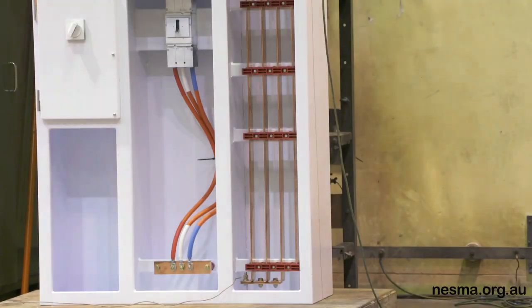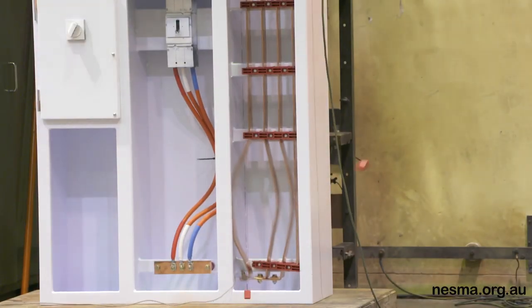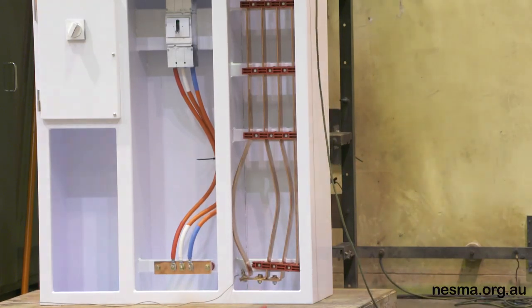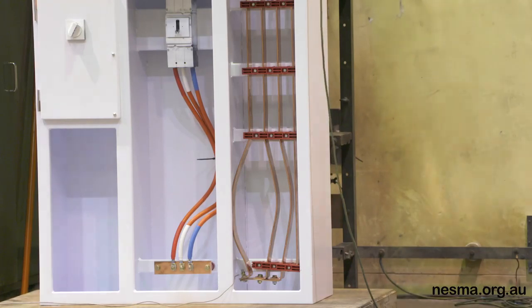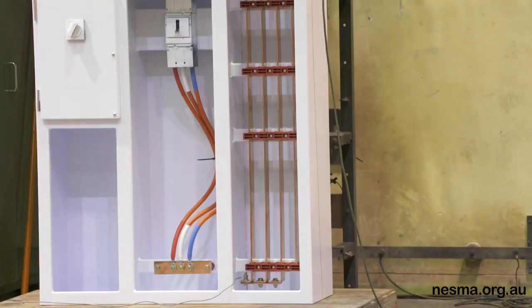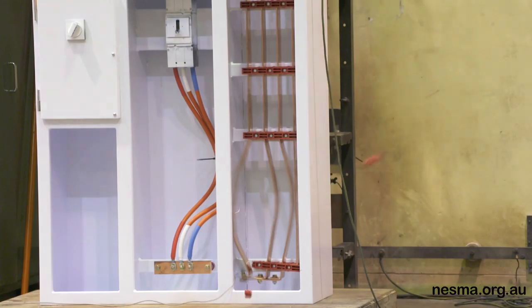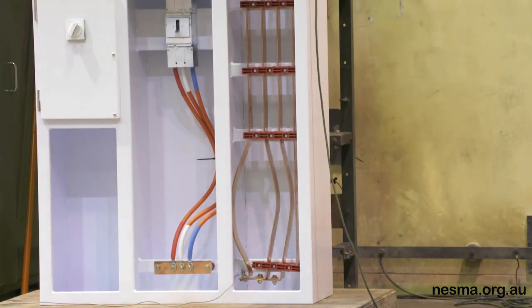The standard itself requires that the busbar system remain sort of intact. As you can see, the bars with the closer busbar support spacing have remained substantially intact, and so this sort of support system would be quite common for a motor control centre where you might have plug-in units, and one of the tests was to ensure that the plug-in unit could still be removed and inserted after the test.